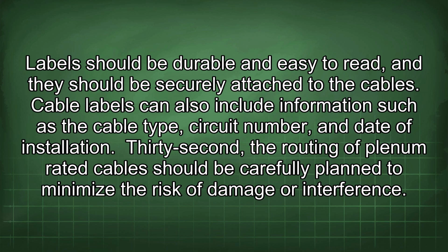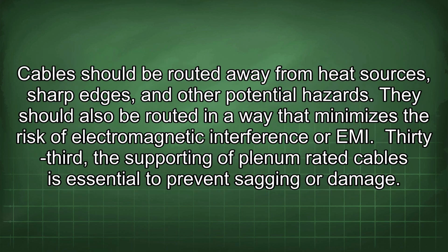32nd, the routing of Plenum-rated cables should be carefully planned to minimize the risk of damage or interference. Cables should be routed away from heat sources, sharp edges, and other potential hazards. They should also be routed in a way that minimizes the risk of electromagnetic interference or EMI.